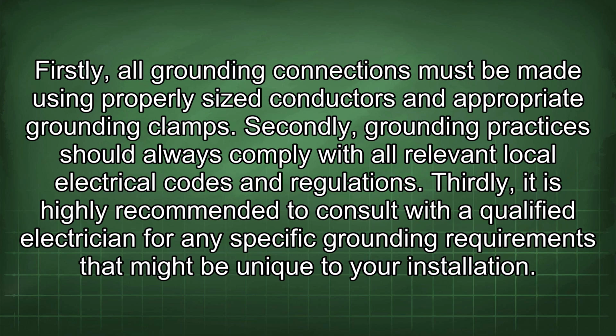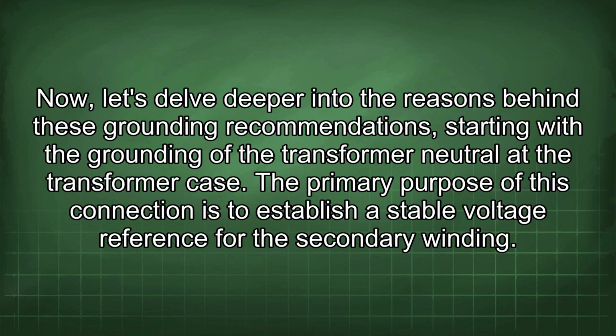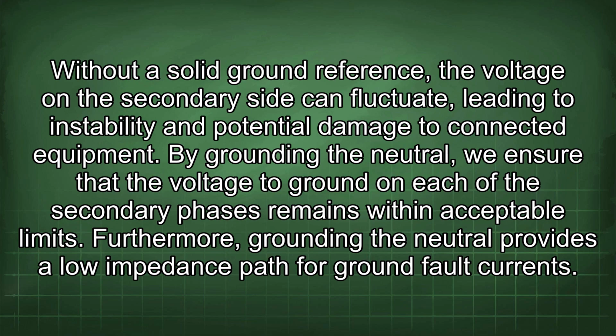Now let's delve deeper into the reasons behind these grounding recommendations, starting with the grounding of the transformer neutral at the transformer case. The primary purpose of this connection is to establish a stable voltage reference for the secondary winding. Without a solid ground reference, the voltage on the secondary side can fluctuate, leading to instability and potential damage to connected equipment. By grounding the neutral, we ensure that the voltage to ground on each of the secondary phases remains within acceptable limits. Furthermore, grounding the neutral provides a low impedance path for ground fault currents.